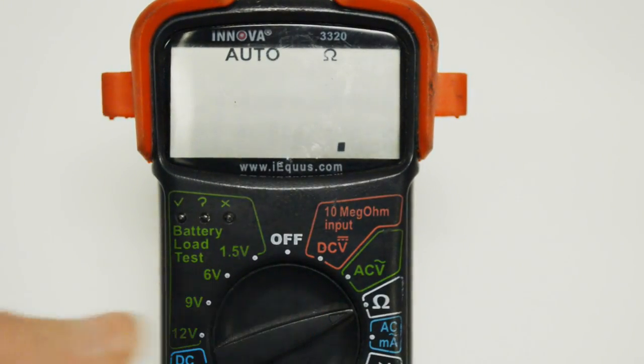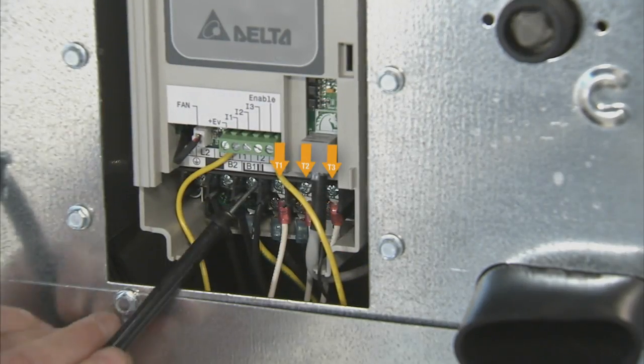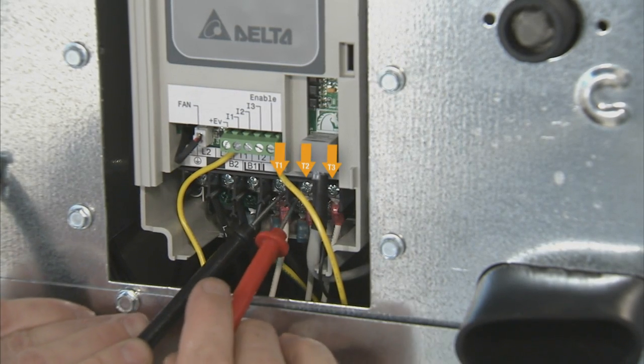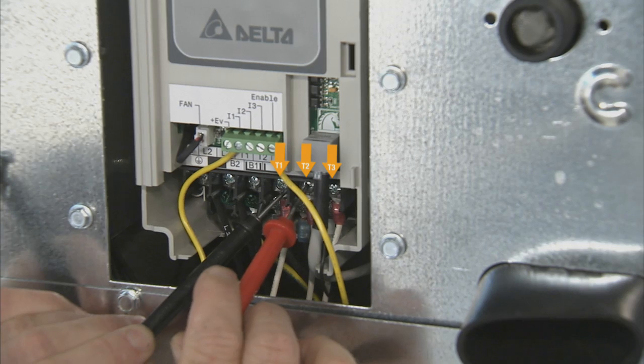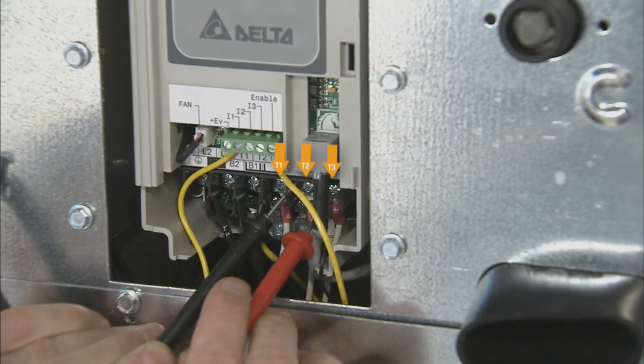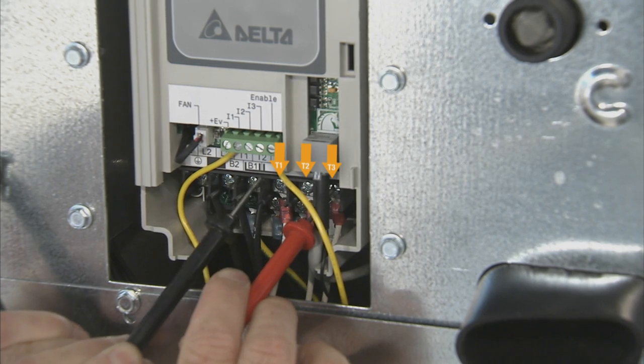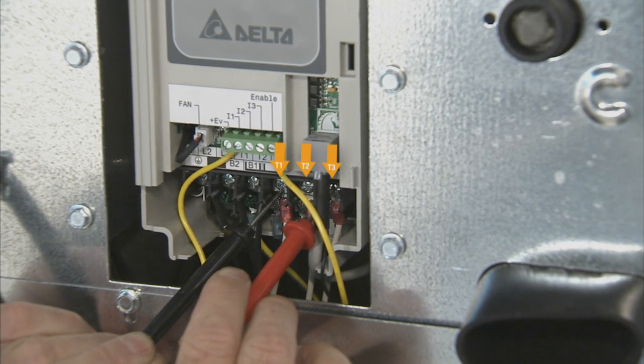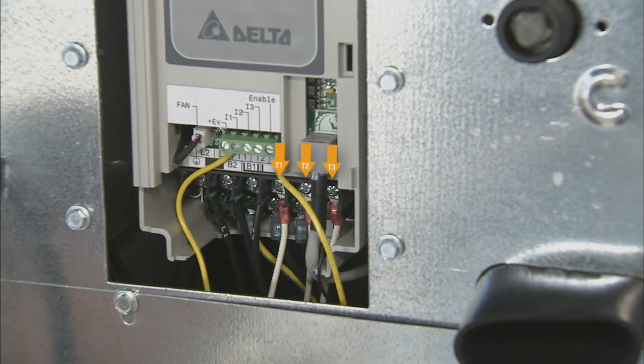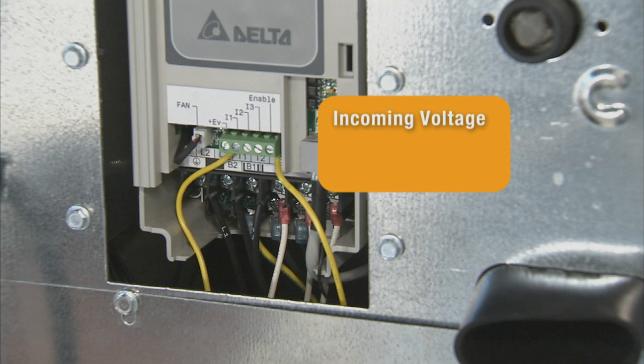Use a voltmeter on the ohms resistance setting. Check the resistance across the motor leads by placing the leads of the voltmeter on each wire, testing between T1 and T2, T2 and T3, and T1 and T3. Check with your local Dexter representative for the resistance values for your specific Dexter model. If the values are outside of the recommended specifications, the motor will need to be replaced to prevent any damage to the new VFD.